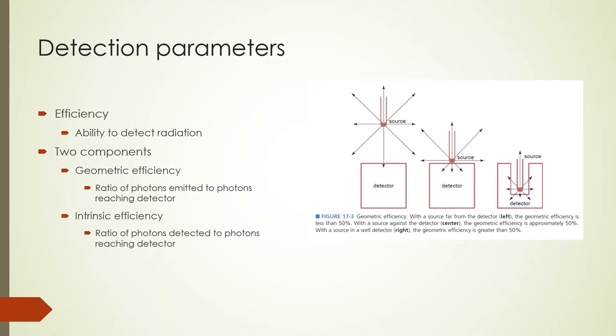In the first image, geometric efficiency is lowest because radiation is emitted in a 360-degree direction, but only a small amount reaches the detector. In the second image, the geometric efficiency is close to 50% because the detector intercepts about half of the emitted radiation. In the last image, a well-type geometry is used. In this arrangement, the detector intercepts more than 50% of the emitted radiation. We shall see this type of geometry when we learn about well counters later.